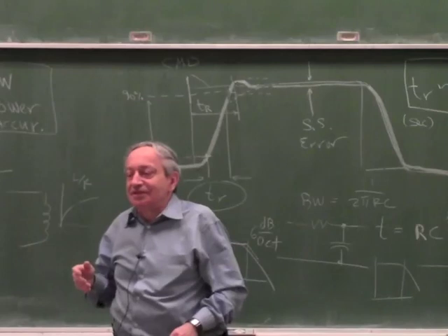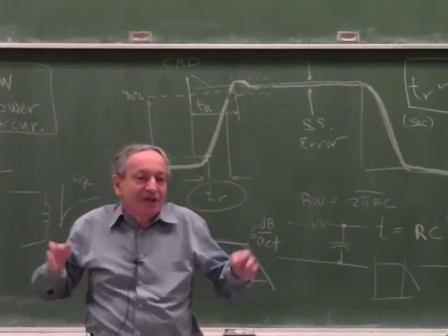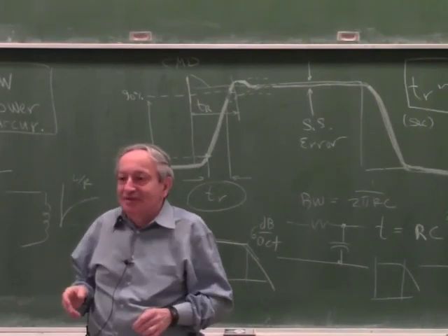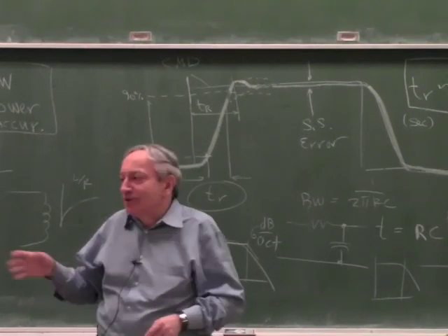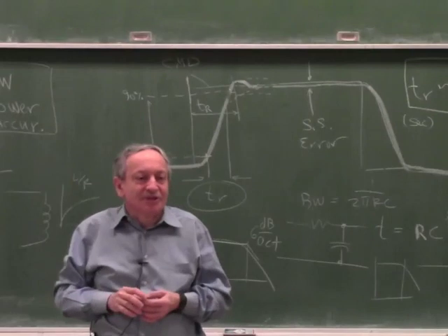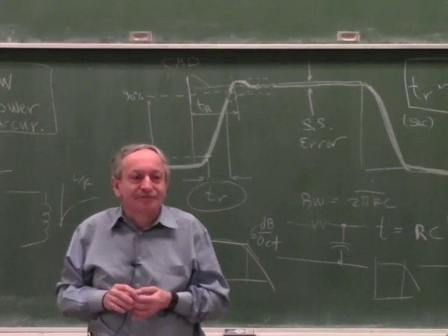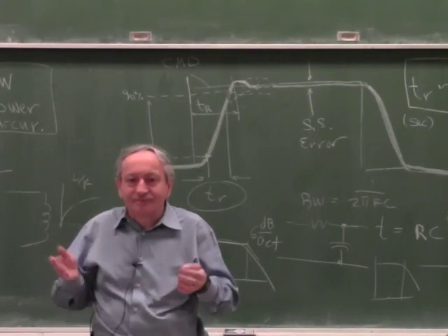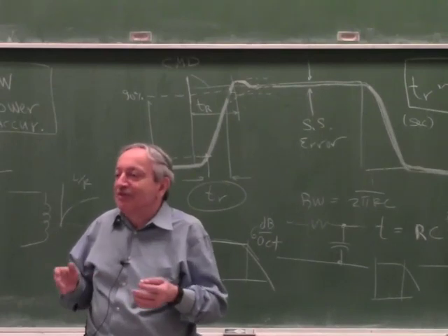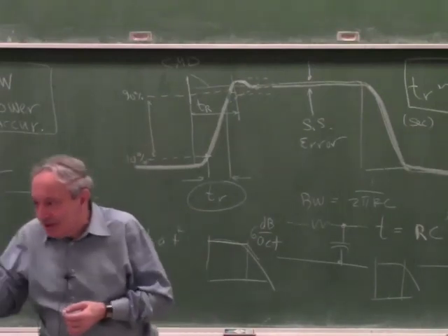And what is the reason, let's see if you remember that, why you need filters at all? Because if you say, I don't care if noise gets through, the actuator cannot respond to the noise. Right? The noise is high frequency, my actuator is very slow, why do I need a filter at all? So there's two reasons, which again we spent a week on. So, why does a servo system need a filter at all? Aliasing. Yes, pardon? Aliasing, very good.